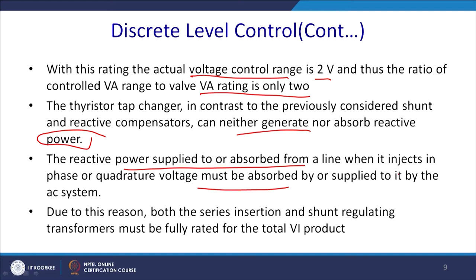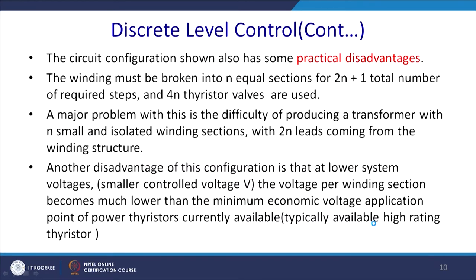Due to this reason, both the series insertion and the shunt regulating transformer must be fully rated to the VI product of the rating. So, the rating is quite high in the case of both the shunt and the series solution. But here, this configuration has some practical disadvantages. The circuit configuration also has some practical disadvantages.